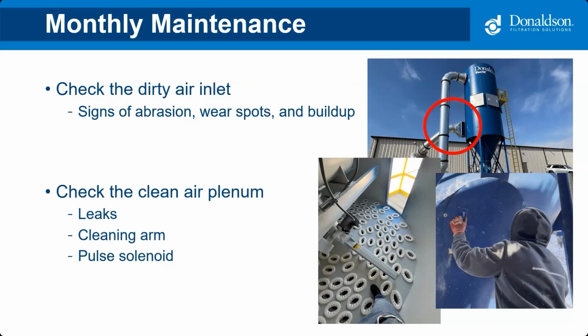Moving on, in the upper right-hand corner, there's a red circle around the dirty air inlet. You're going to want to inspect the dirty air inlet, looking for signs of abrasion or leakage. If you have any dust buildup, that's a great indication that something's leaking or something's not sealed properly. So just do a visual check there to make sure that's still airtight.